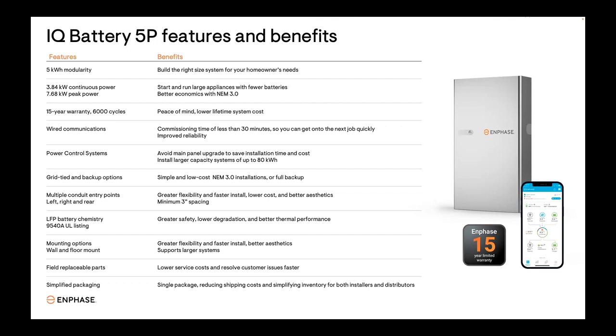We are continuing to use the same safer and more reliable battery chemistry called LFP, or lithium iron phosphate. It is still in the lithium ion family of chemistries, but it has some distinct differences and advantages compared to the other common chemistries like NMC, nickel, manganese, cobalt, which is the most common chemistry used by our competitors. LFP chemistry has, as I said, greater safety. It doesn't have the same level or the same risk of thermal runaway if there are flaws in the manufacturing of the cells, or if there's some sort of damage to the battery.